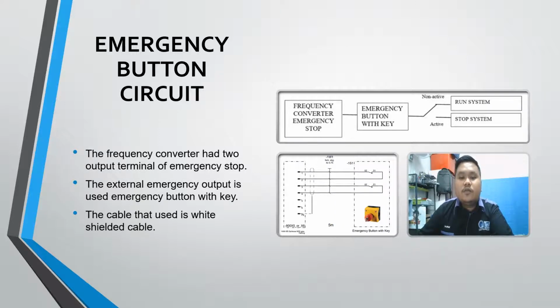I would like to continue the presentation with the subtopic of emergency button circuit. The purpose of the emergency button is to stop the machinery quickly when there is a risk of injury or the workflow requires stopping. All machinery requires an emergency button unless it will not reduce the risk or the machine is hand operated. An emergency button must be highly visible in color and shape and must be easy to operate in an emergency situation.